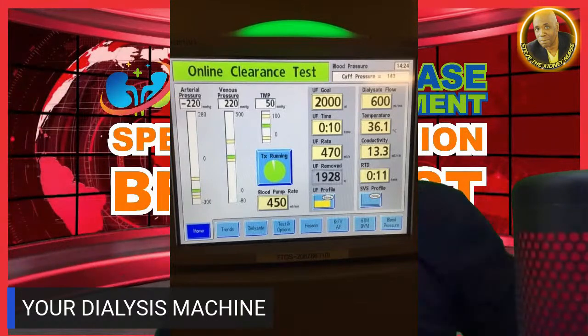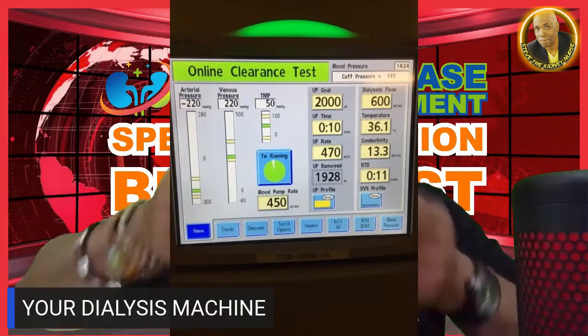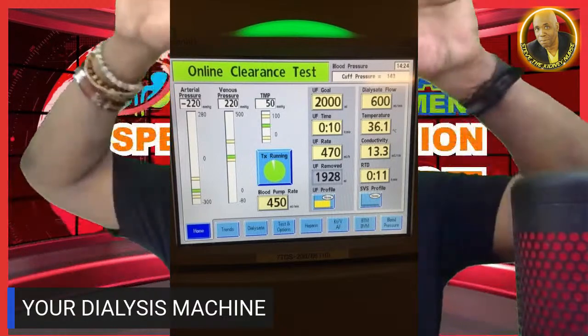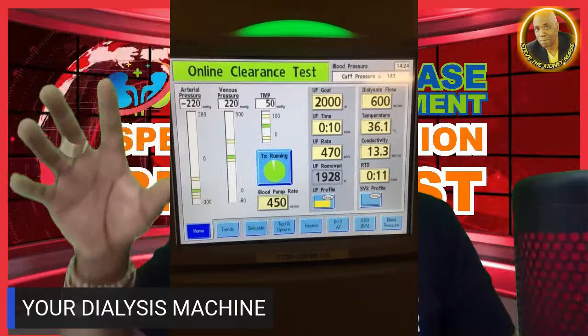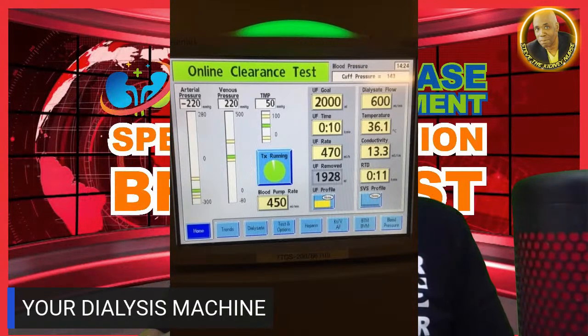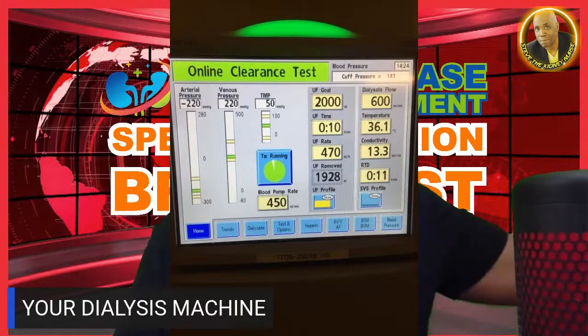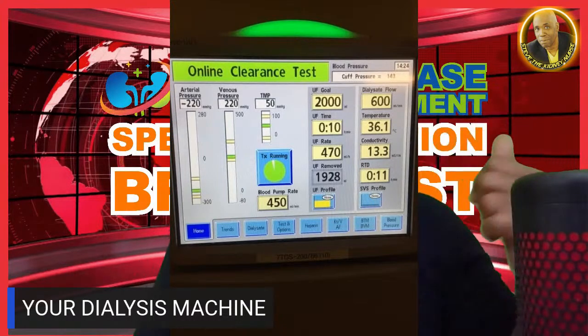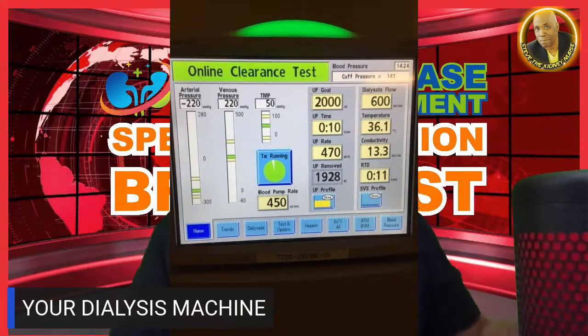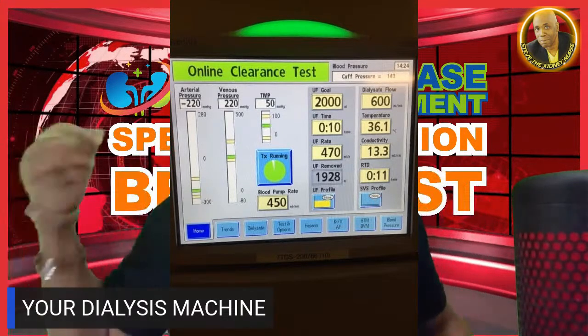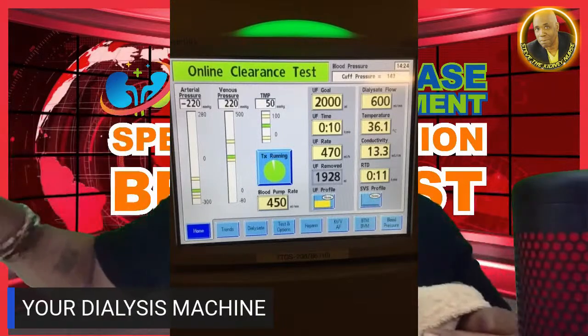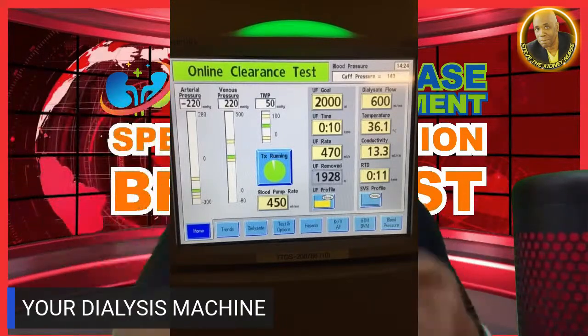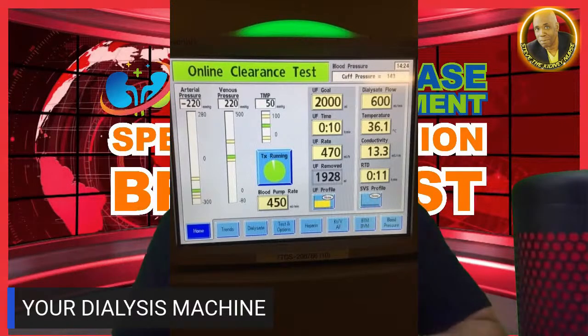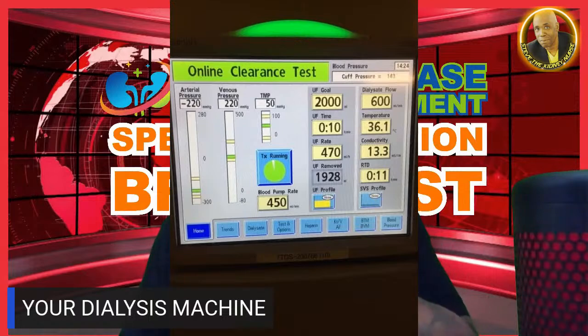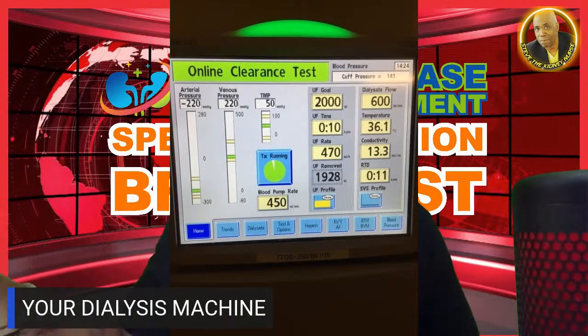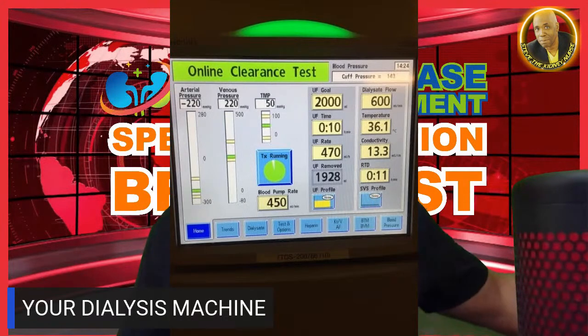So when you come back on, they hook you up, and you're getting fluid that's already in the machine, the saline. And now when you go back on, the machine goes back to where it left off, and it's not going to pull the correct amount of fluid off. So that's why you've got to pause the machine so it doesn't pull any fluid. When you come back, you restart the treatment. They do that to a lot of patients. And when you get off the machine, you may not even hit your target weight.